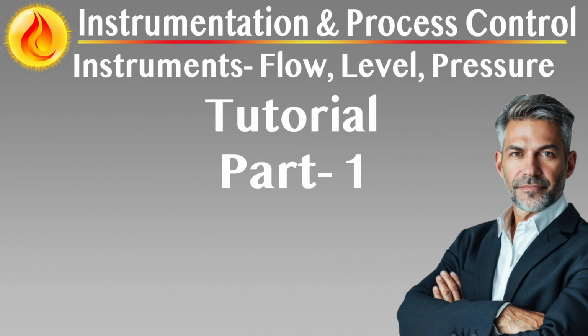For digital integration, Modbus RTU is the preferred protocol between DCS and subsystems, e.g. analyzers, offering robust serial communication in master-slave configurations. Until fully standardized fieldbus architectures are universally adopted, project-specific proprietary digital protocols from approved DCS vendors are acceptable, provided TCOO evaluation supports the limited vendor flexibility they impose.